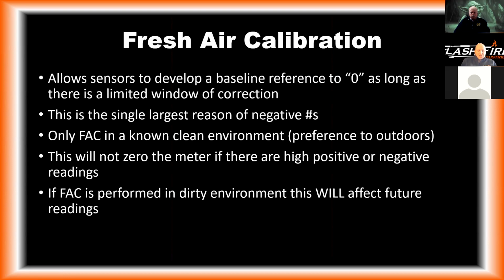So my recommendation, and this is going to be different based on the manufacturer. If another manufacturer told you different, it's not that they're wrong and I'm right. It's that every meter is different. I would start the meter up as soon as you get the call. Let the meter warm up in the apparatus while you're driving to the incident. When you get to the incident, you can get onto the front lawn.